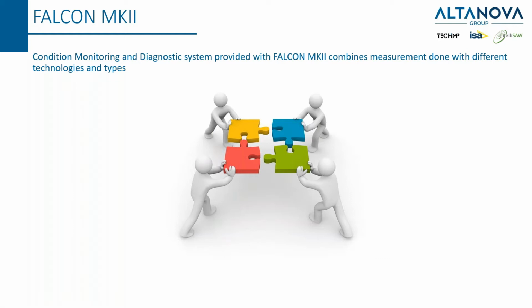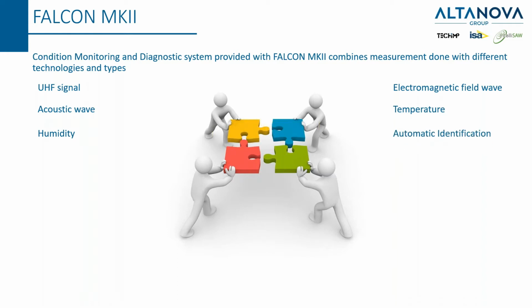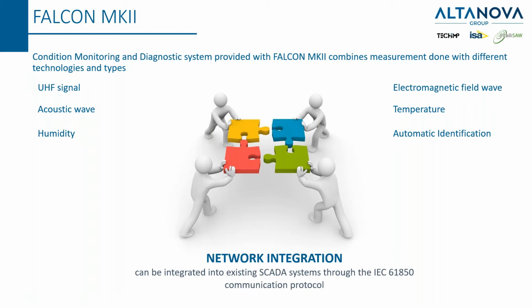This Falcon Mark II unit basically combines measurement done with different technology and types. We are talking actually of a unit that is merging different sensor technology and measurement. In fact, the Falcon Mark II can get a signal from UHF, from electromagnetic field wave, from acoustic wave, can also have humidity measurement, temperature measurement, and actually it has the automatic identification as for the Falcon Mark I. And it's also important to note that, like the Falcon, it has communication facilities like network integration using IEC 61850.